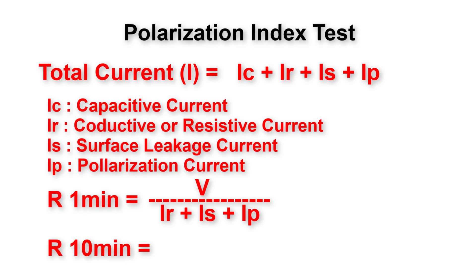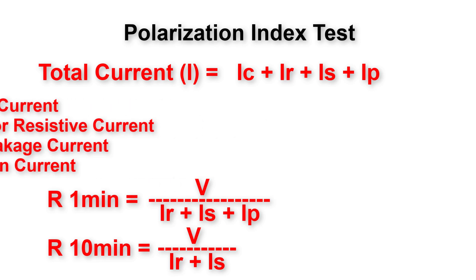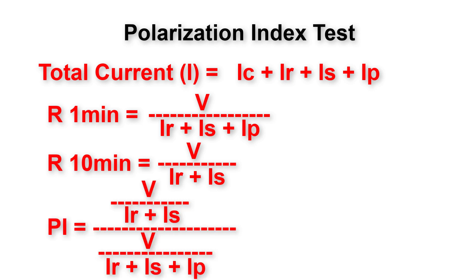The megger reading at 10 minutes is without polarization current, so R(10 min) = V / (Ir + Is). Therefore the polarization index PI equals R(10 min) / R(1 min), which equals [V / (Ir + Is)] / [V / (Ir + Is + Ip)]. Simplifying, this gives us: (Ir + Is + Ip) / (Ir + Is), or equivalently 1 + Ip / (Ir + Is).